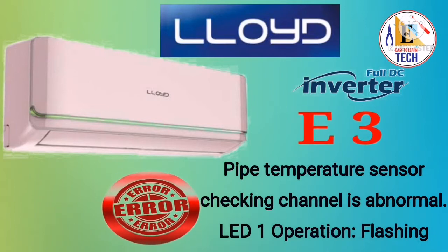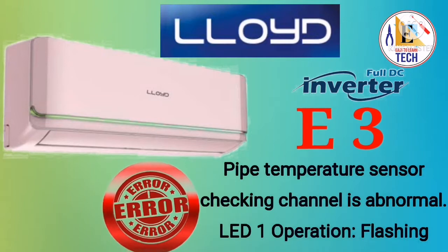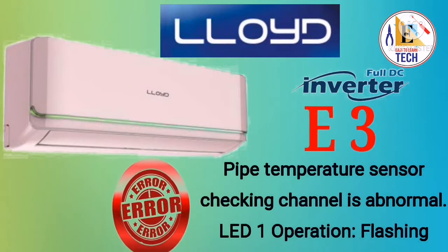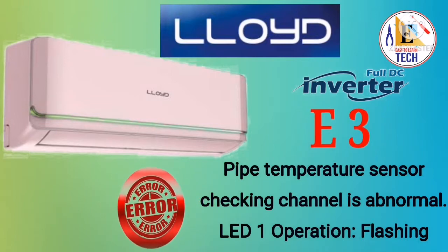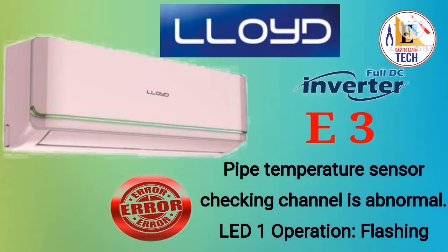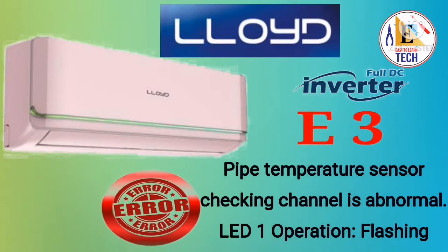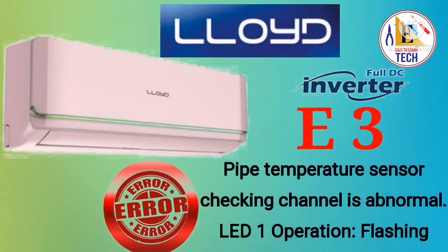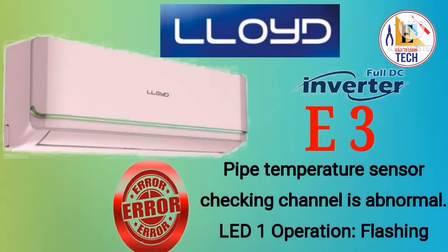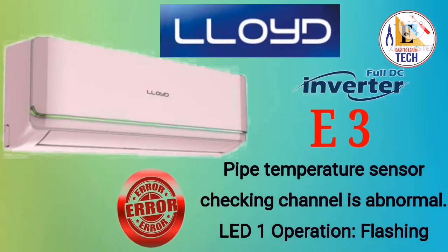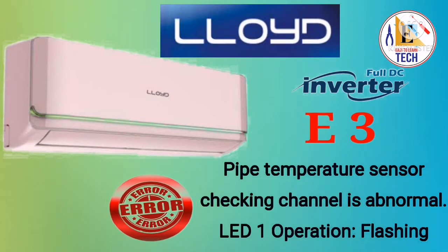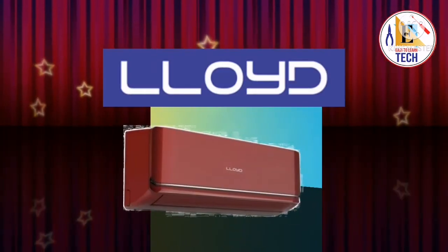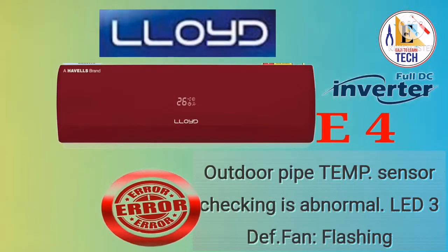Then you have to check the resistance of your sensor. If the resistance is good, then you have to check whether the output supply coming from the PCB is good or not. If the output supply from the PCB is not coming good, then you have to change the PCB and your unit will be working and you will get the solution for the error E3 and the LED1 operation light flashing. Let's see the next error code.